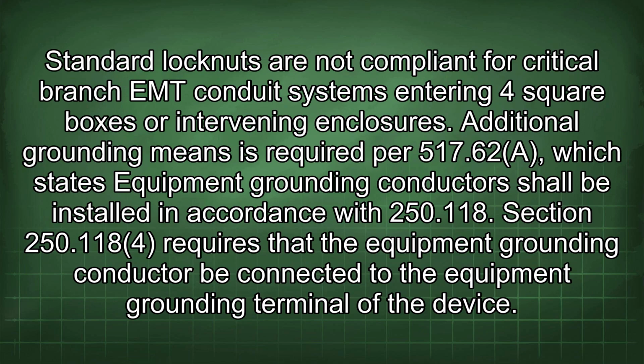Standard locknuts are not compliant for critical branch EMT conduit systems entering 4 square boxes or intervening enclosures. Additional grounding means is required per 517.62A, which states equipment grounding conductor shall be installed in accordance with 250.118. Section 250.118 requires that the equipment grounding conductor be connected to the equipment grounding terminal of the device.